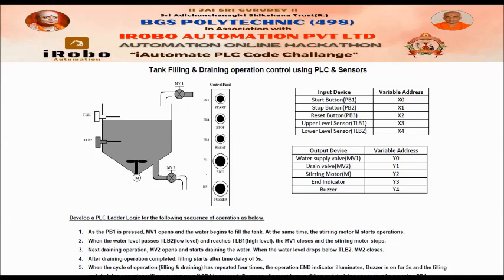One filling and draining sequence constitutes one cycle, and this cycle should be repeated 4 times. After 4 cycles of filling and draining, the end indicator (Y3 output) turns on continuously. The buzzer is on for 5 seconds only, then turns off. The filling and draining operation will not restart even if PB1 is pressed again. Only by pressing the reset button PB3 can the filling and draining restart.